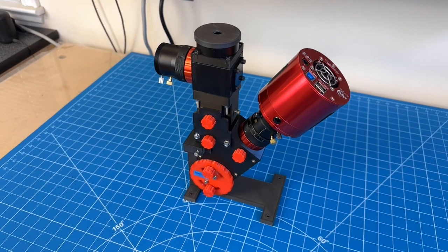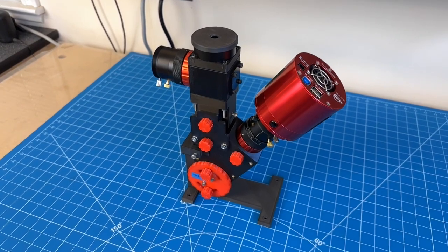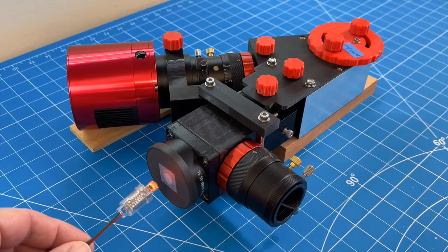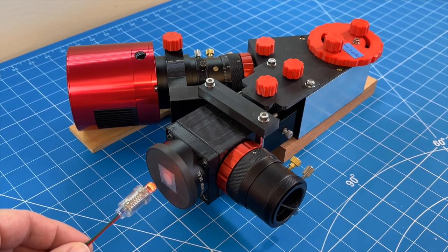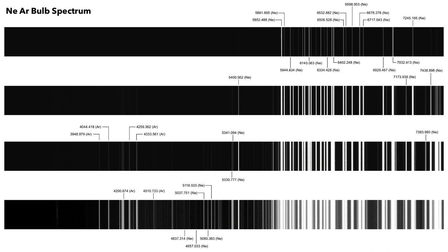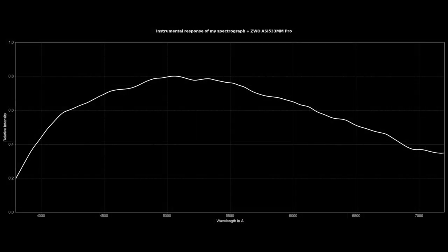To calibrate the 2D spectrum in wavelength, I captured the emission spectrum of a calibration lamp — in my case a neon argon bulb. And to calibrate it in intensity, I had to calculate the instrumental response of the spectrograph.